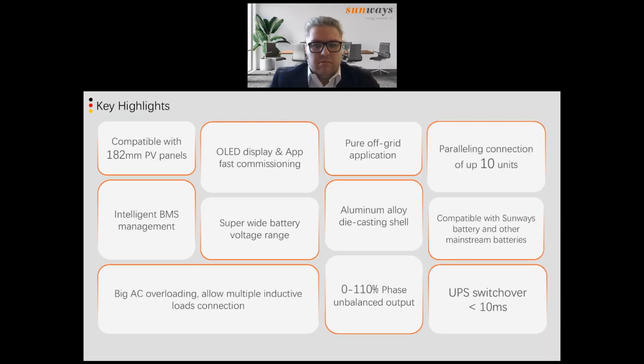As I mentioned, it can be connected up to 10 units, and the UPS switchover is less than 10 milliseconds. That's very important for markets that suffer from instability in the grid, so we can be very secure with the system. The build of the inverter itself is well prepared for harsh environments.